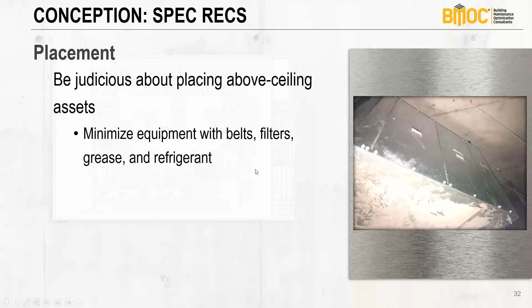Minimize equipment with belts, filters, grease, and refrigerant above a ceiling, period. When you can, put it in a mechanical room, on the floor where it's easy to maintain. In that mechanical room, don't put too much stuff in it. Ensure there are clearances. I've seen mechanical rooms with very little space where everything was piled on top of itself with no clearance. Watch for that too.